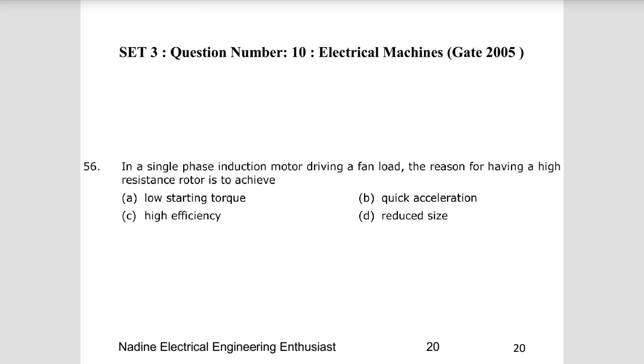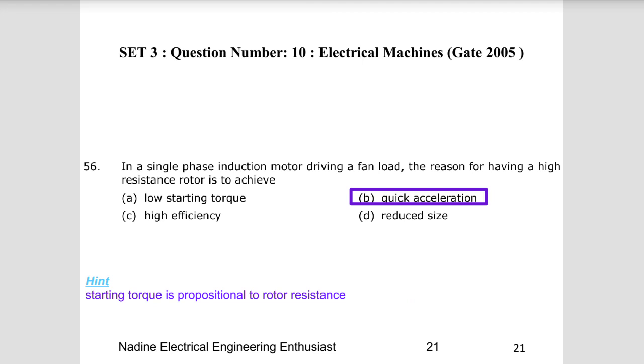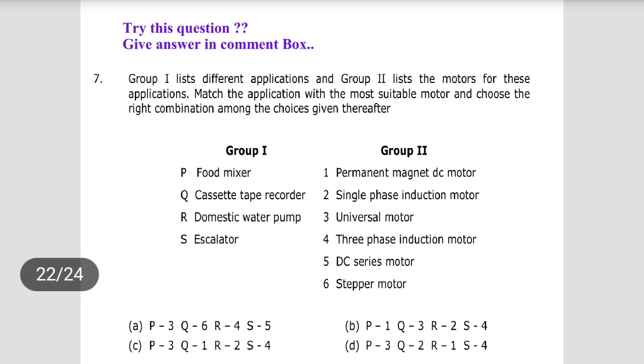Tenth question: in a single-phase motor driving a fan load, the reason for having a high-resistance rotor is to achieve quick acceleration. Starting torque is generally proportional to rotor resistance, so a high rotor resistance gives quick acceleration. This is similar to a slip ring induction motor, which provides high starting torque due to high rotor resistance, whereas a squirrel cage motor has better running performance but lower starting torque.